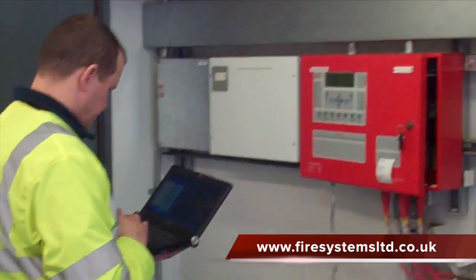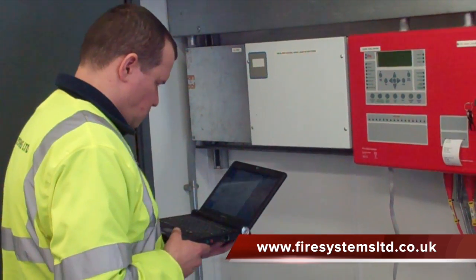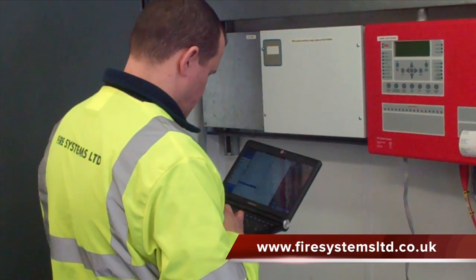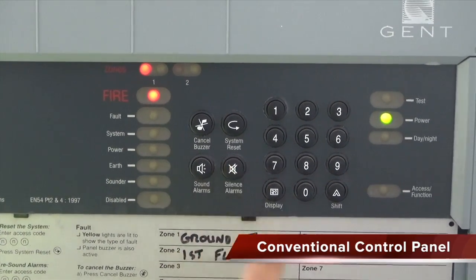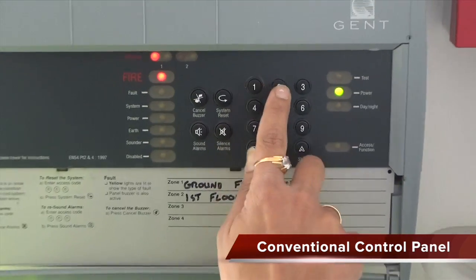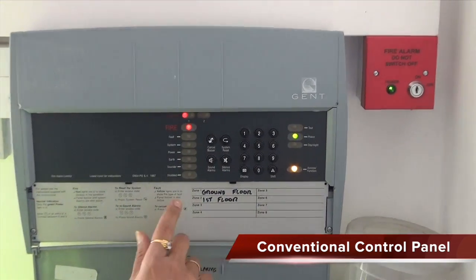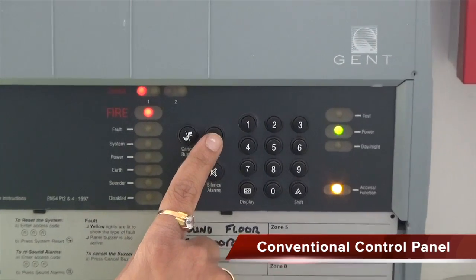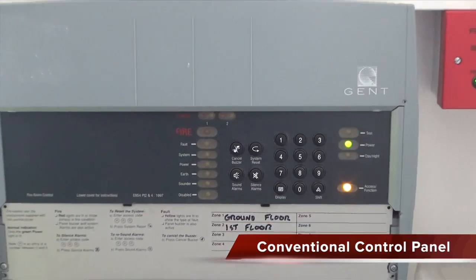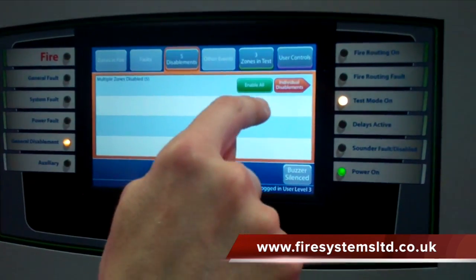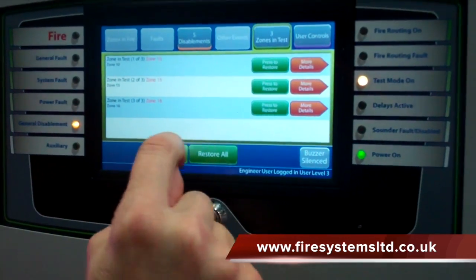Is an addressable system right for you? When answering this question, you have to consider your choices — between a conventional and an addressable system. Conventional systems are predominantly used for small installations of no more than 20 detectors. The only real benefit of choosing a conventional system over an addressable is that on small systems it's between 30 to 50 percent cheaper. However, on systems over 20 devices, addressable systems are by far the best choice in many different ways, including the cost.